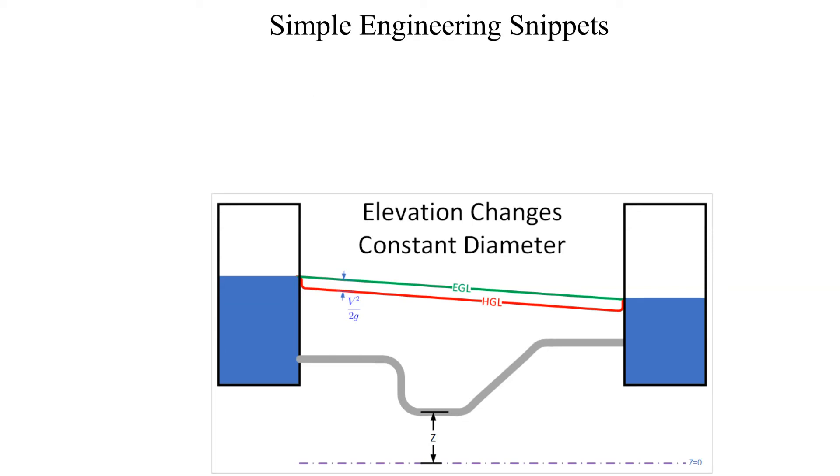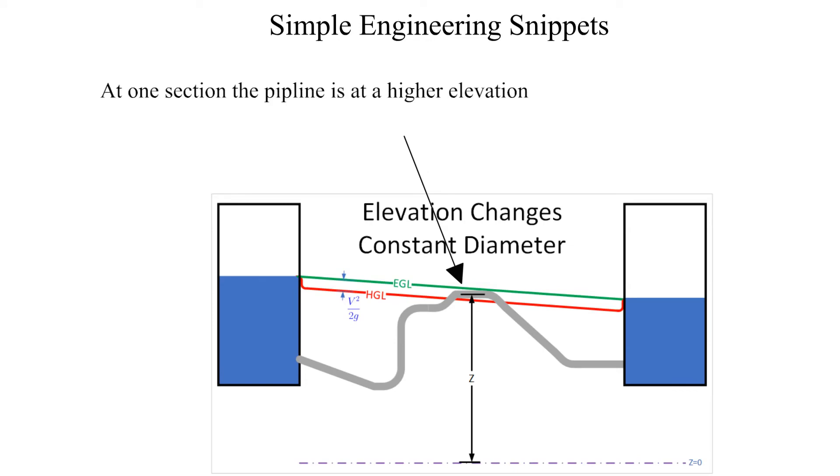Now let's consider the case with a different pipeline elevation profile. In one section the pipeline is at a higher elevation than the hydraulic grade line, which indicates that the pressure is negative. In future instructional videos we will cover why this is undesirable if not outright an unacceptable design.